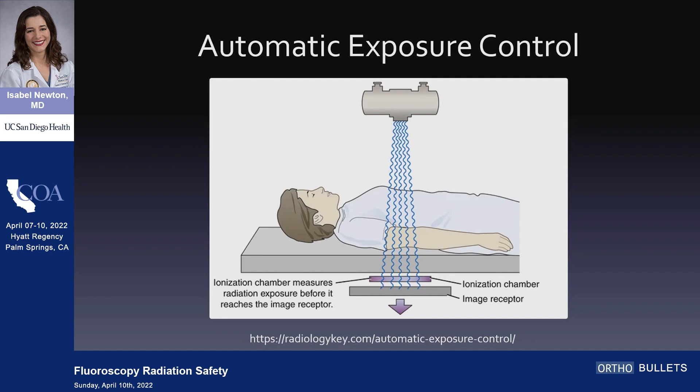The automatic exposure control is really important for you to know because you use things that are very high density. If you leave a surgical instrument in the field and it doesn't really need to be there, your AEC is pumping photons because it's trying to get something to drive through this thing that's impenetrable. So keep that in mind.